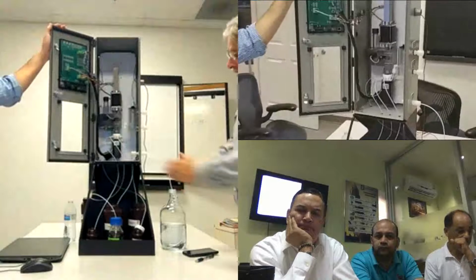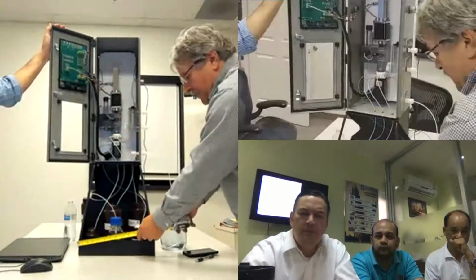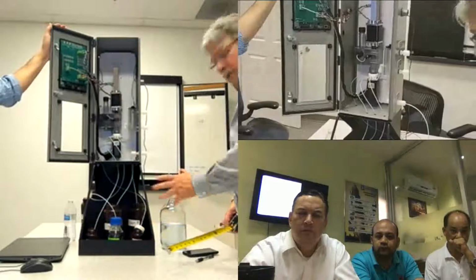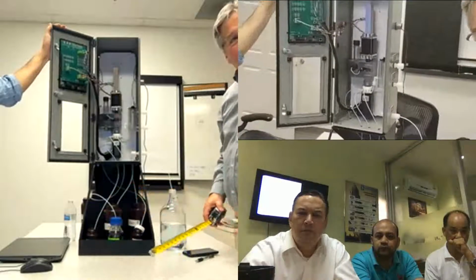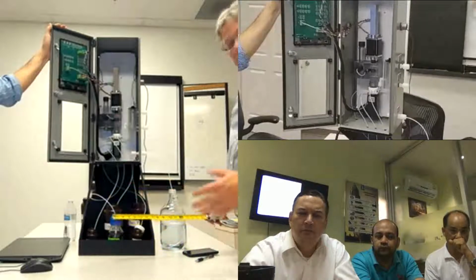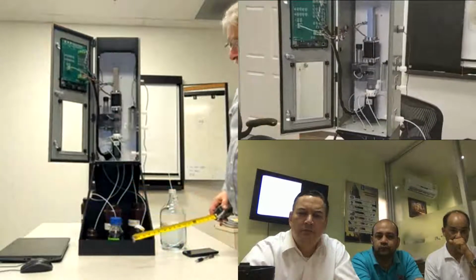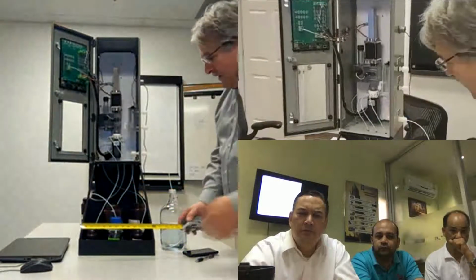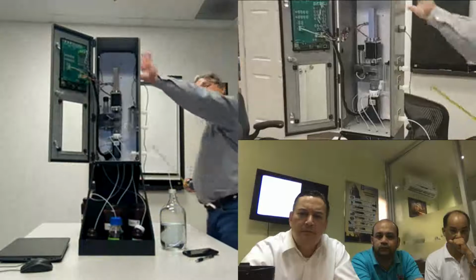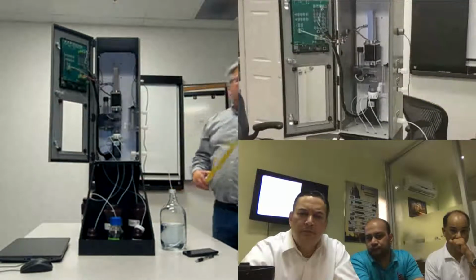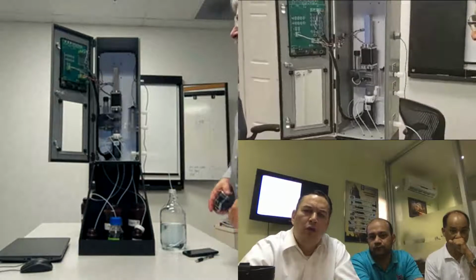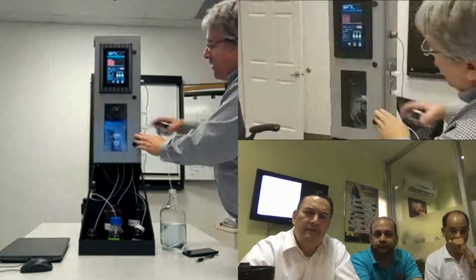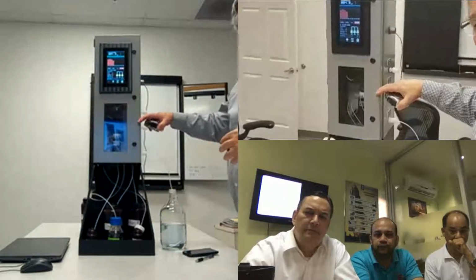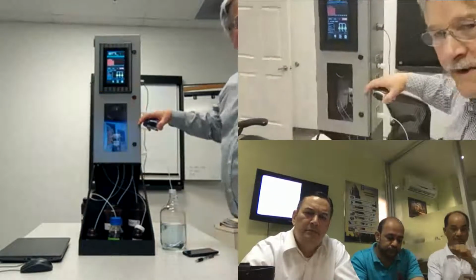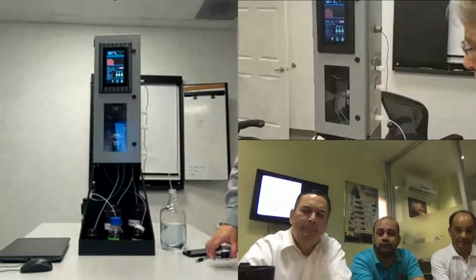8.5 by 24 inches by 8.5 wide—that's just this section here. Then you have the area down here where the carboys are, where you store your reagents. We don't store them like this normally, we just did this for the demonstration. There are standard carboys, black bottles you can get, and they fit in this bottom chamber. There are mounting brackets on the back of the box so you can mount it to a panel. I think the small width is really good because every power plant I've been to has rows and rows of these things, so you can fit a lot more in a smaller space.